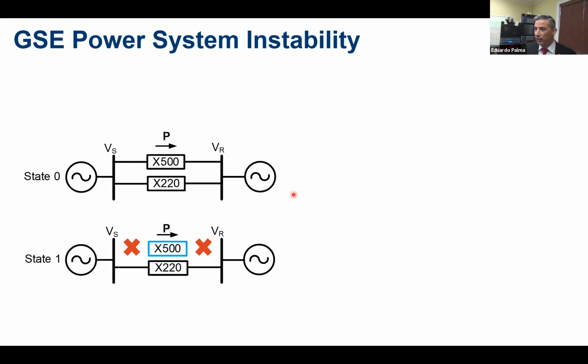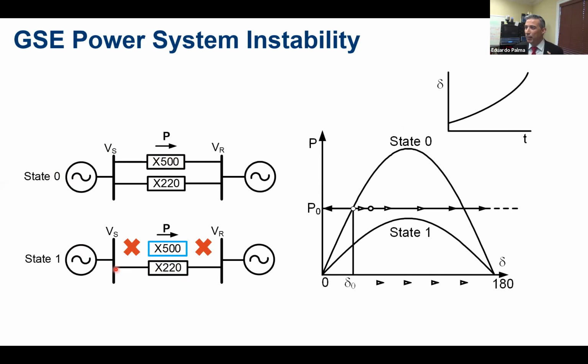So in other terms, if we have the 500 kV line connected, but all of a sudden this 500 kV line loses connection, then we have to use an alternate path, which is the 220 kV transmission lines. So we call state 0 when everything is stable and everything is connected. But state 1, how do we manage for state 1 to maintain the equilibrium? Well, as we know, the power that is being transported needs to still get to the loads or to the capital. But the angle of the power system, the electrical degrees, is going to change. So compensating means that we need to lessen the loads so that the 220 kV network can transport energy to its destination.